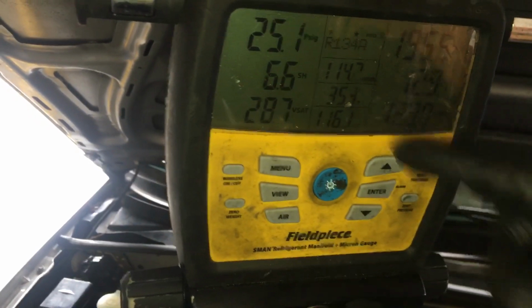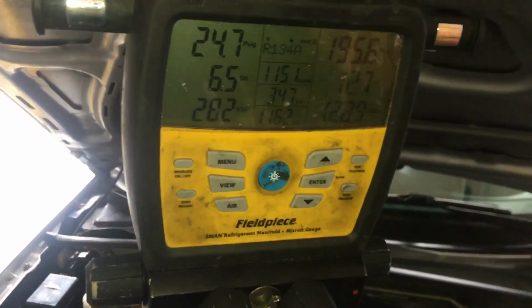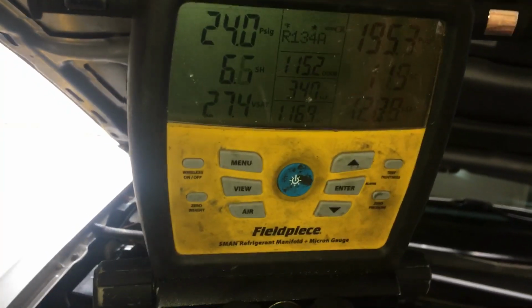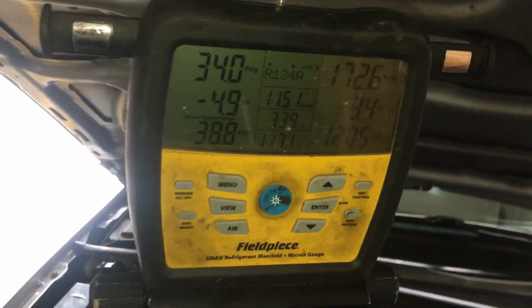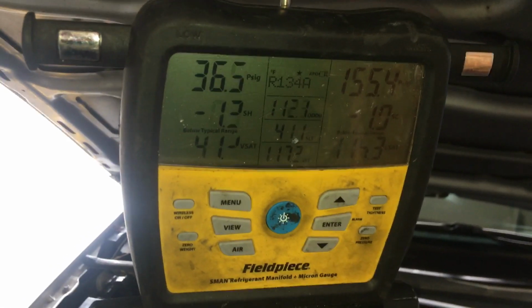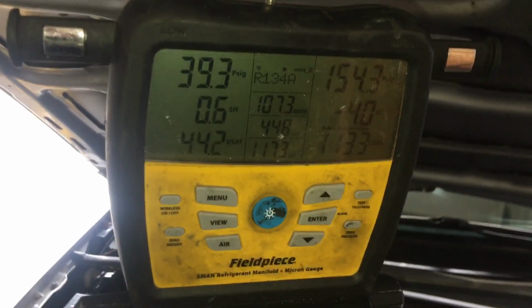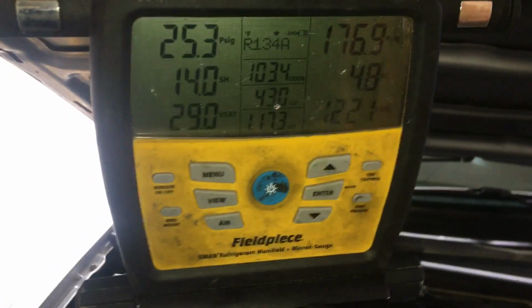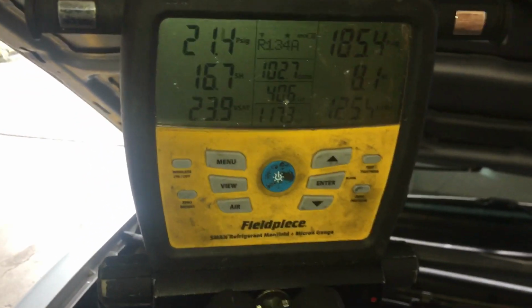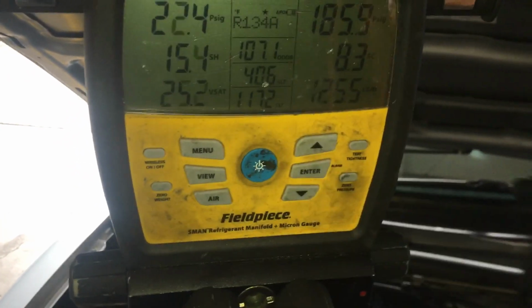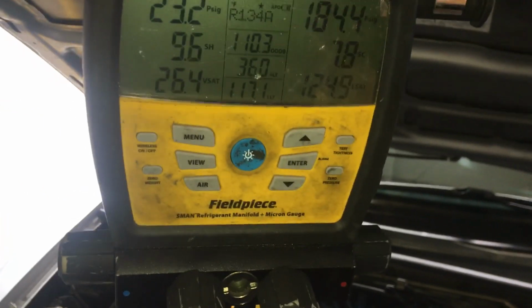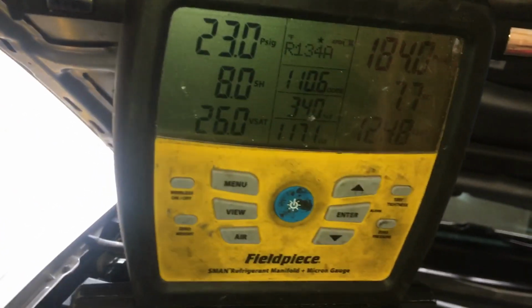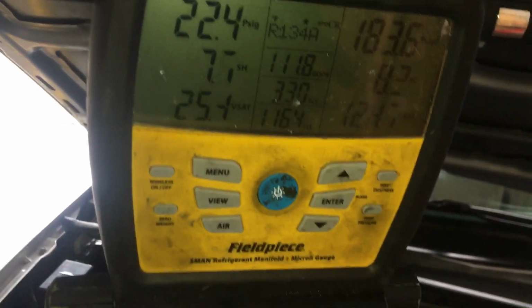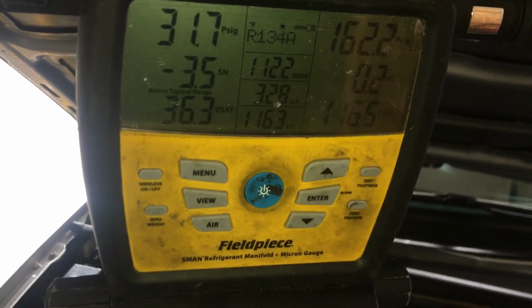When we get towards 32 degrees, our compressor will cycle off. Look at that, our superheat and subcooling changing. Boom, there, just turned off. So that's the compressor turning off. And we'll watch it there, just turned on. Because there's no load, this 117 degree air is no longer feeding the evaporator. It's the cool air inside feeding the evaporator. And the high RPM, because we're at 1500 RPM.